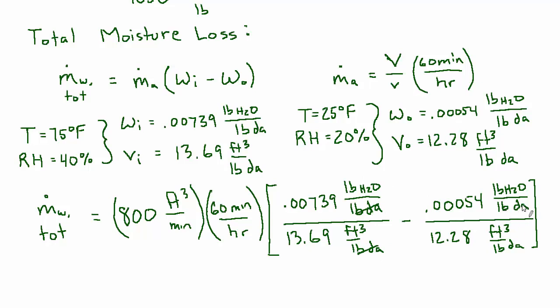So what you might notice here is the pounds of dry air terms cancel out and what you end up with is pounds of water per cubic foot, which is the absolute humidity. So the distinction between humidity ratio and absolute humidity, which are often used interchangeably but are not the same thing: humidity ratio is pounds of water per pound of dry air, and absolute humidity is pounds of water per cubic foot. It's per unit volume. So for example, when I use the psychrometric calculator which is able to give these very precise numbers, it can also give absolute humidity. So you could shortcut this process and just look up the absolute humidity, pounds of H2O per cubic foot, and skip over having to do this. But I show it this way because in a test environment you're using the psychrometric chart, you probably won't be able to pull absolute humidity directly from the chart. It's usually not offered, so this is the way you're going to do it.